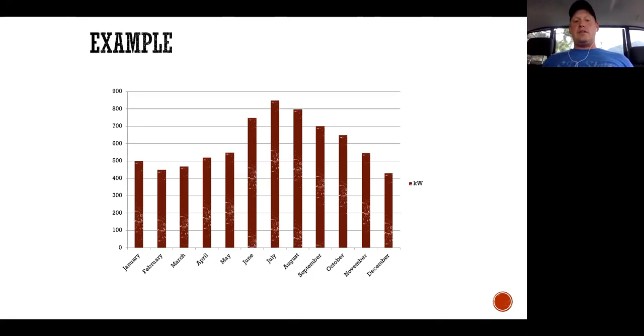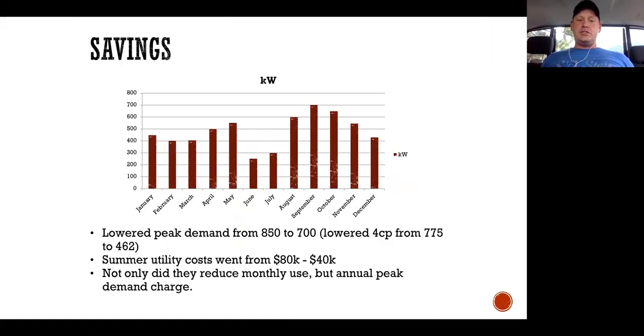That one impact saved that school $60,000 in energy savings. All they did was move from peak demand time to early in the morning - I can talk about that - but they also closed their outside air dampers. I know this is a lot of information, but this year we showed their summer costs alone went from 80,000 to 40,000 by reducing the way they operated during the summer months. That's a no-cost behavior change.